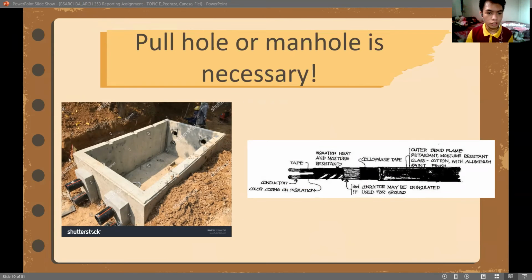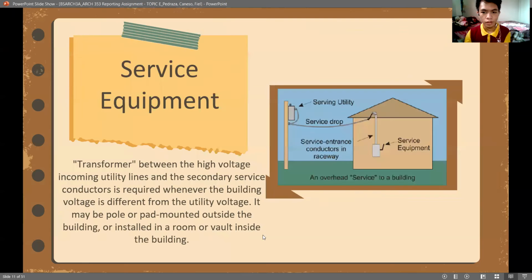When underground electric wiring is duct installed and the run extends over several hundred feet, a pulling handhole or manhole is necessary. This is often used for high voltage cable. Cable usually used is the SE type, U or USE. Service equipment. A transformer between the high voltage incoming utility lines and the secondary service conductors is required whenever the building voltage is different from the utility voltage. It may be pole or pad mounted outside the building or installed in a room or vault inside the building.